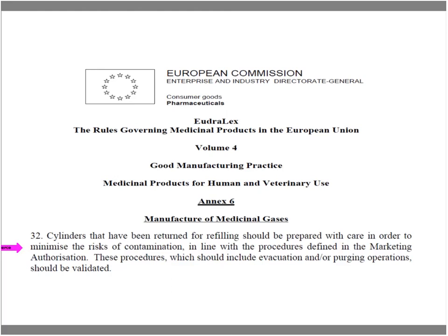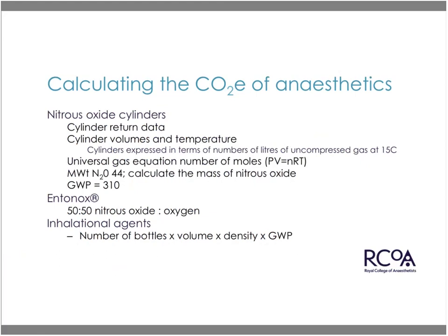And these procedures specifically should include evacuation and or purging operations, and these should be validated. Well, the significance of this is that if one knows and has record of the cylinder numbers that are returned for refilling, then by definition we can conclude exactly how much of each medical gas has been used in that cycle from manufacture to patient cylinder return.